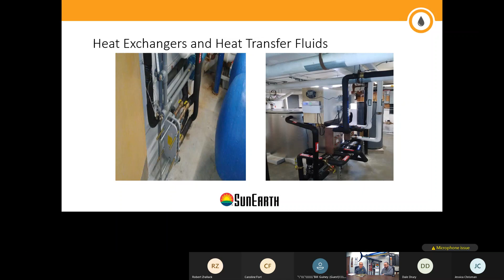The definitions are in different code books. So yeah, one way to mitigate that is with backflow preventers, but those present other annual inspections. So that's one way of satisfying some AHJs. But the double wall heat exchangers are accepted everywhere. Yeah, that's a safe bet. Yeah, when you're using fluids that are considered non-potable or don't fit into the definition that the code states as generally regarded as safe, that is subject to interpretation. We'll just leave it at that.